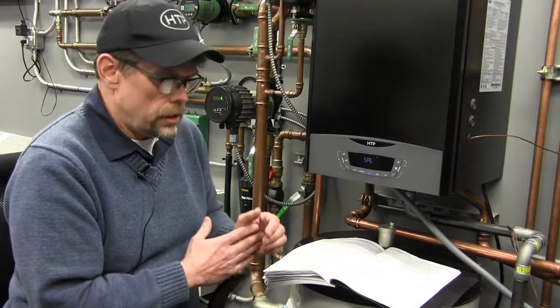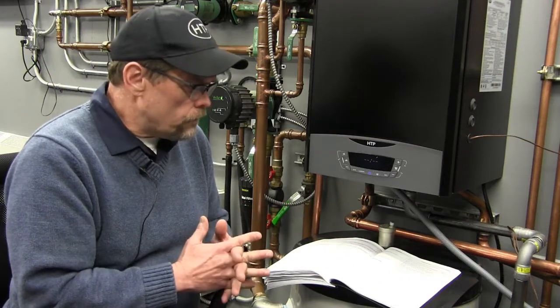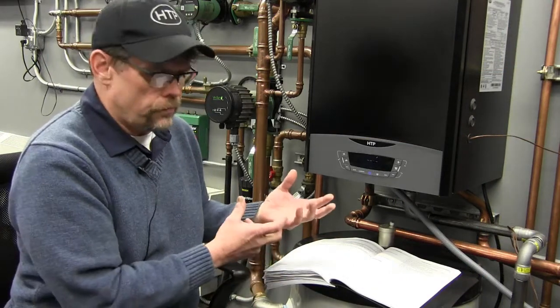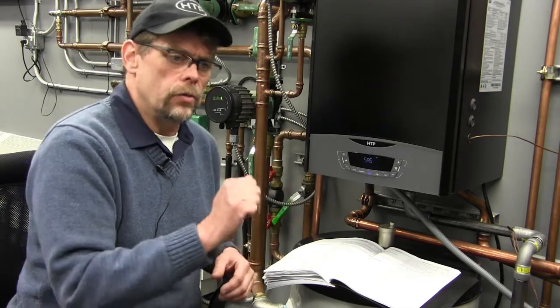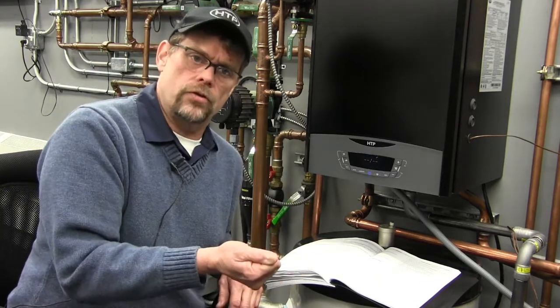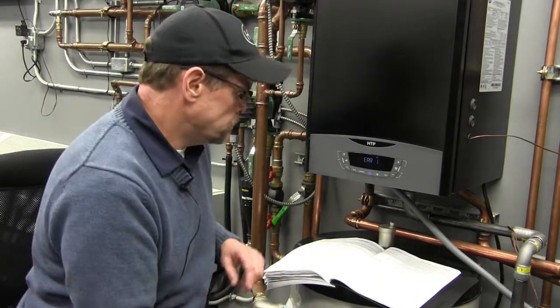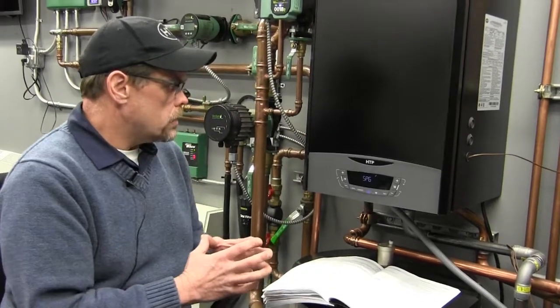Actually, that was a fault that I put in. Of course, when you first fire off and commission a boiler, you want to start it with the gas valve off to make sure that the safety device will shut it off. So these error codes can be used in a couple of different ways. Number one, and the most obvious, is when the boiler is experiencing an error condition.